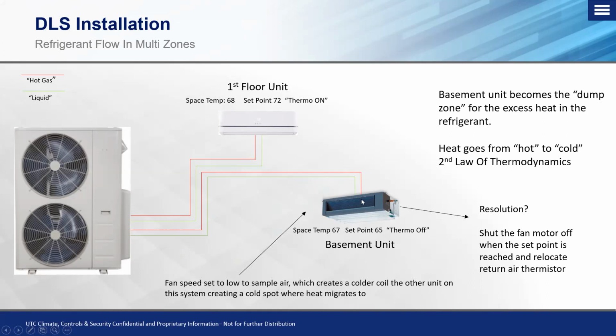This isn't applicable for every single job out there. To be honest with you, we're really not going to see an application where one of the units isn't going to be a space temperature concern. But if you do have an application like this, this is one step or one action that we can take to try to offset a unit overheating by playing around with different fan speeds.